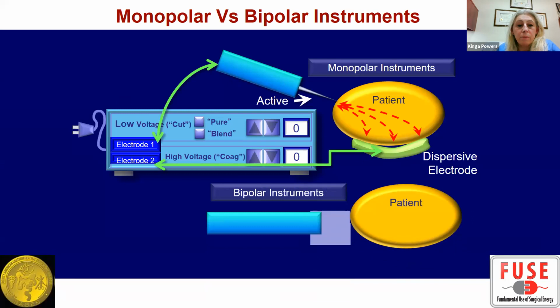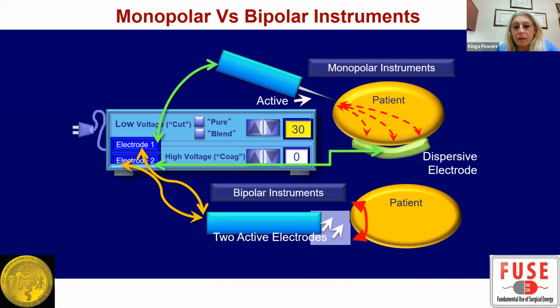In the bipolar instrument system, it contains both electrodes in the circuit right at the patient. To complete the circuit, the only part of the patient involved is that which is between the jaws of the instrument, immediately adjacent to the two electrodes in between here.